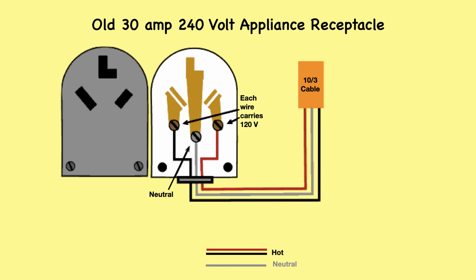A 3-wire cable is needed to carry two 120 volt wires, and a neutral return for a total of 240 volts. This arrangement makes it possible to power the heating elements in the appliance, using the two 120 volts combined, and 120 volt alone to power timers and lights. The smallest cable allowed for use with a 30 amp circuit is 10 gauge, but 8 gauge may also be found in some of these circuits. The circuit is wired to a dedicated 30 amp circuit breaker.